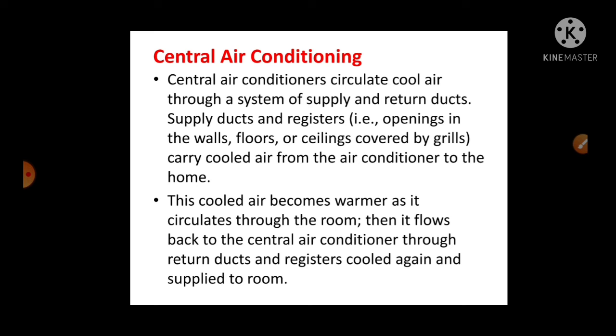Some ventilated air or fresh air is added to this cold air to maintain the purity and quality of the air inside the room. So about 70 to 80% of the air is recirculated, and 15 to 20% fresh air is added to the recirculated air for maintaining the purity of the air.